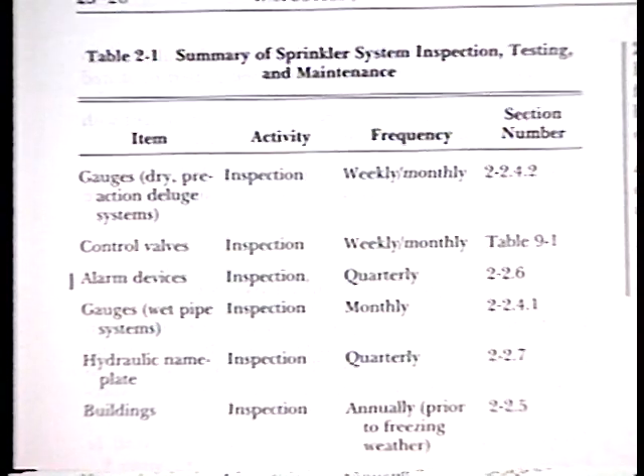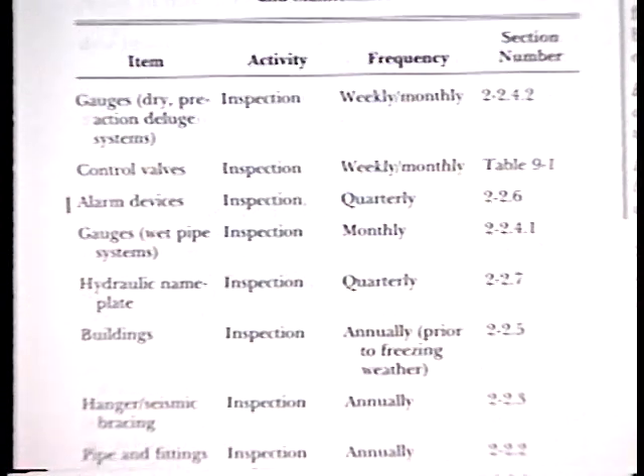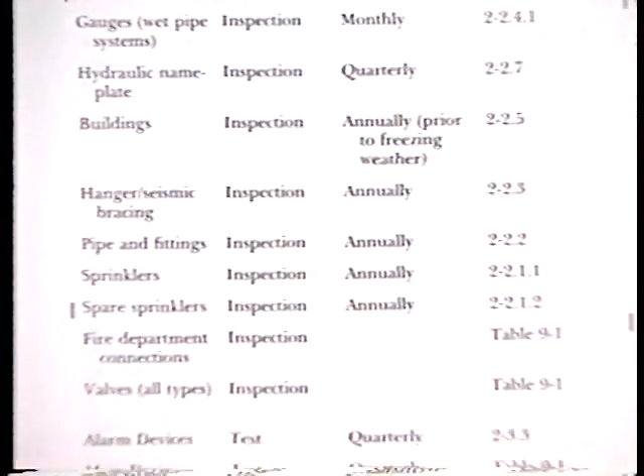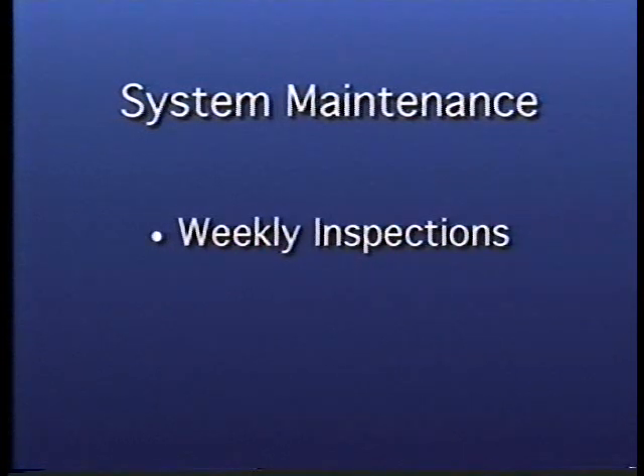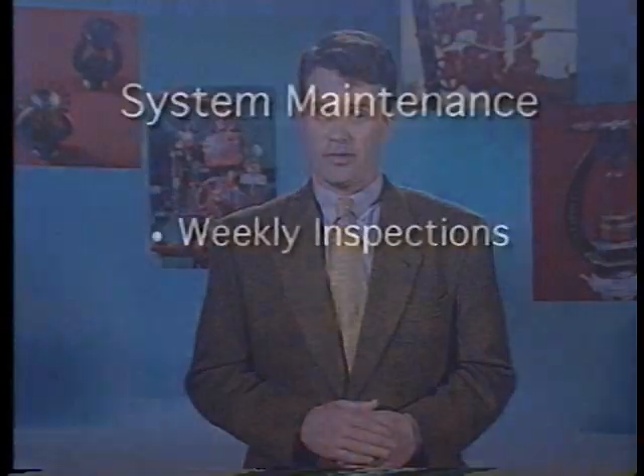Inspection and tests of automatic sprinkler systems are summarized in Table 2-1 taken from NFPA 25. Inspections generally are to be scheduled on a weekly basis. These inspections are visual observations of each listed item and are intended to verify that no obvious changes have occurred in the protected facility or the sprinkler system that could prevent proper performance. Testing entails more specific actions.